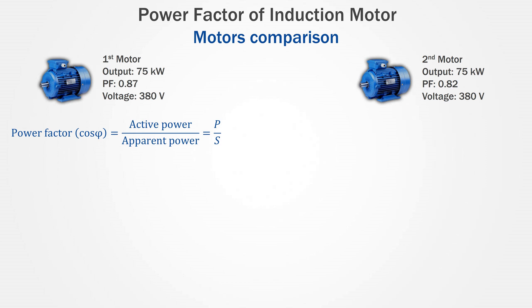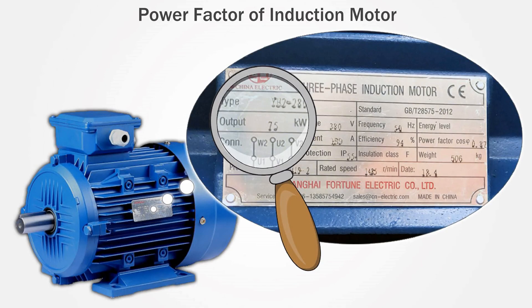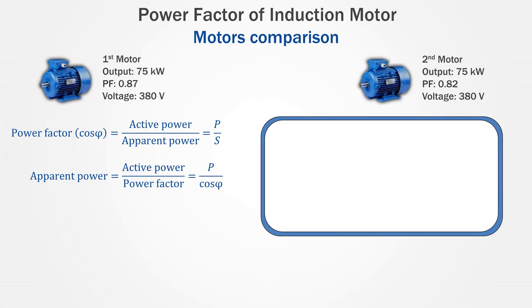Power factor is the ratio between real and total power in a circuit, and by transposing this formula we can get the apparent power. But first we need to do some calculations. The nameplate shows 75 kW, but this doesn't mean the motor actually delivers 75 kW — the actual load will determine the power output. If the motor is fully loaded, the input will be larger than the rated power because the motor has losses. So we need to know the input power, and to find it we use the efficiency formula. Transposing that formula gives us the input power.